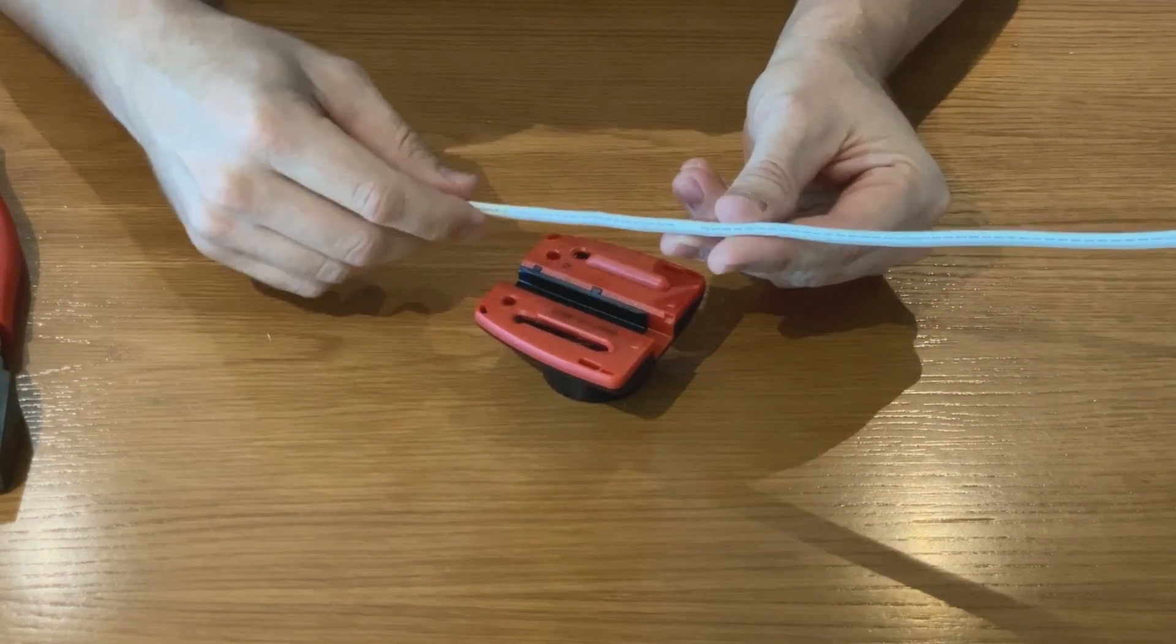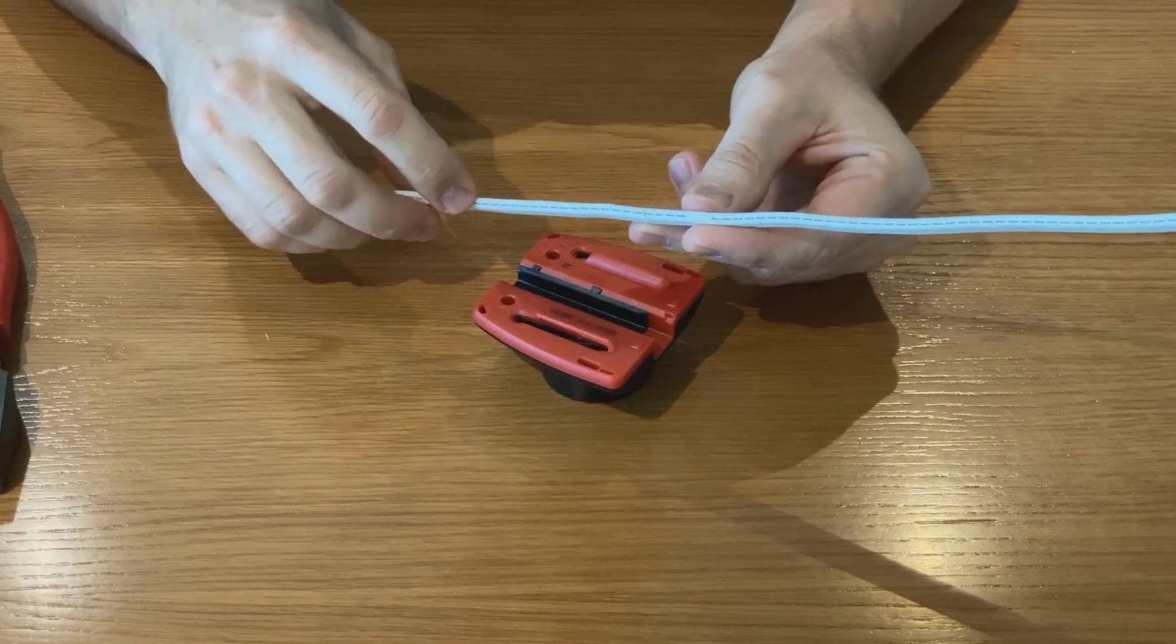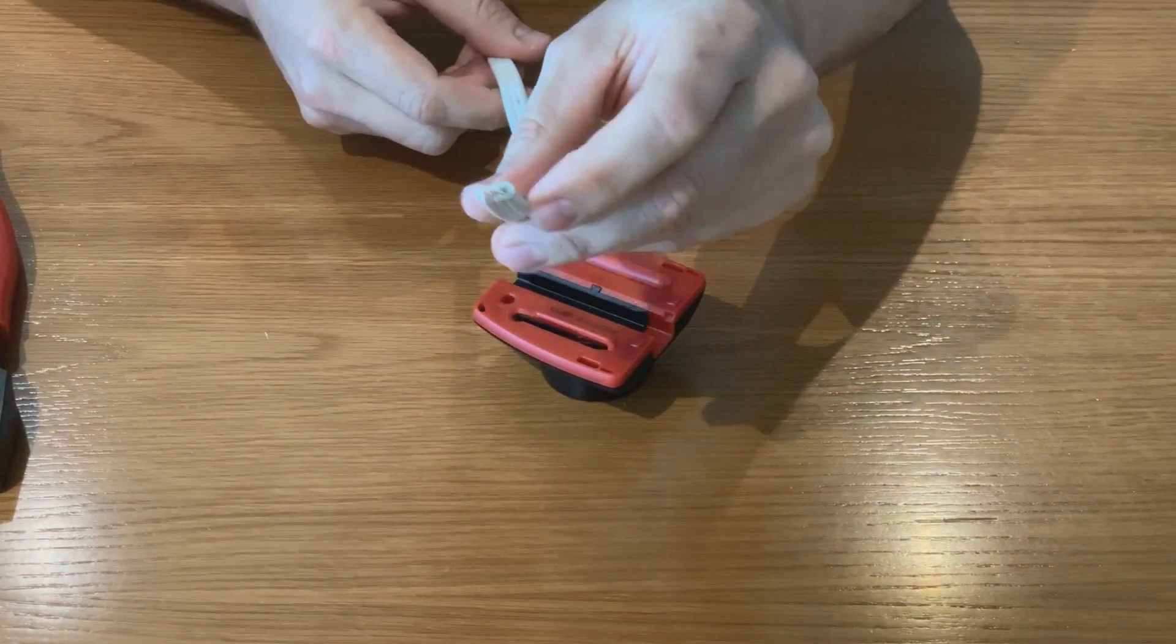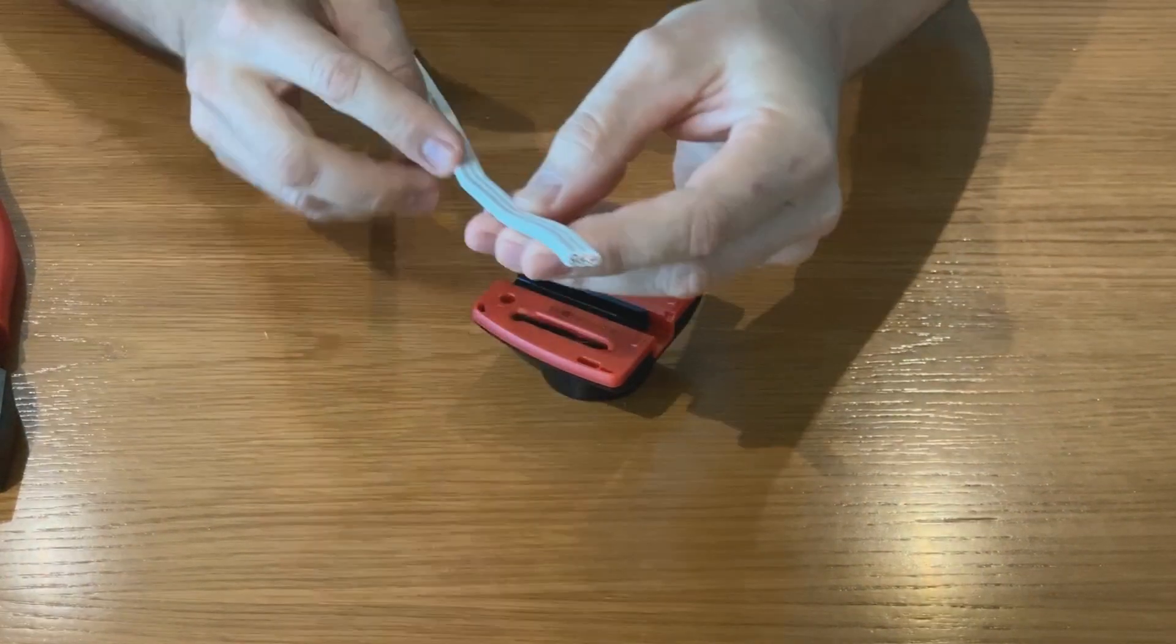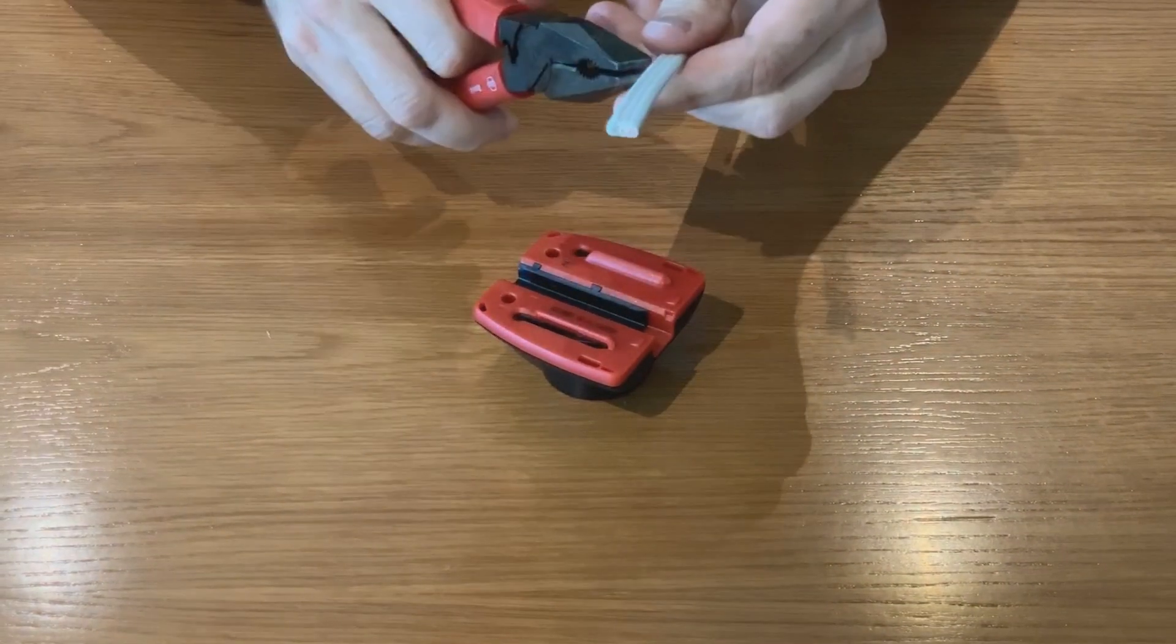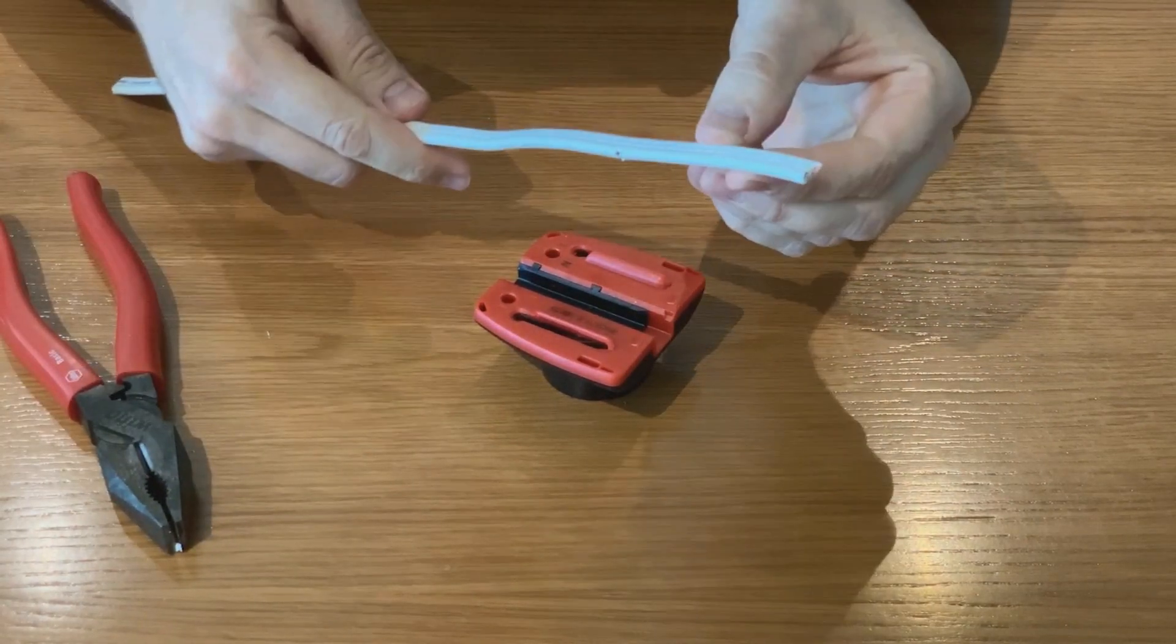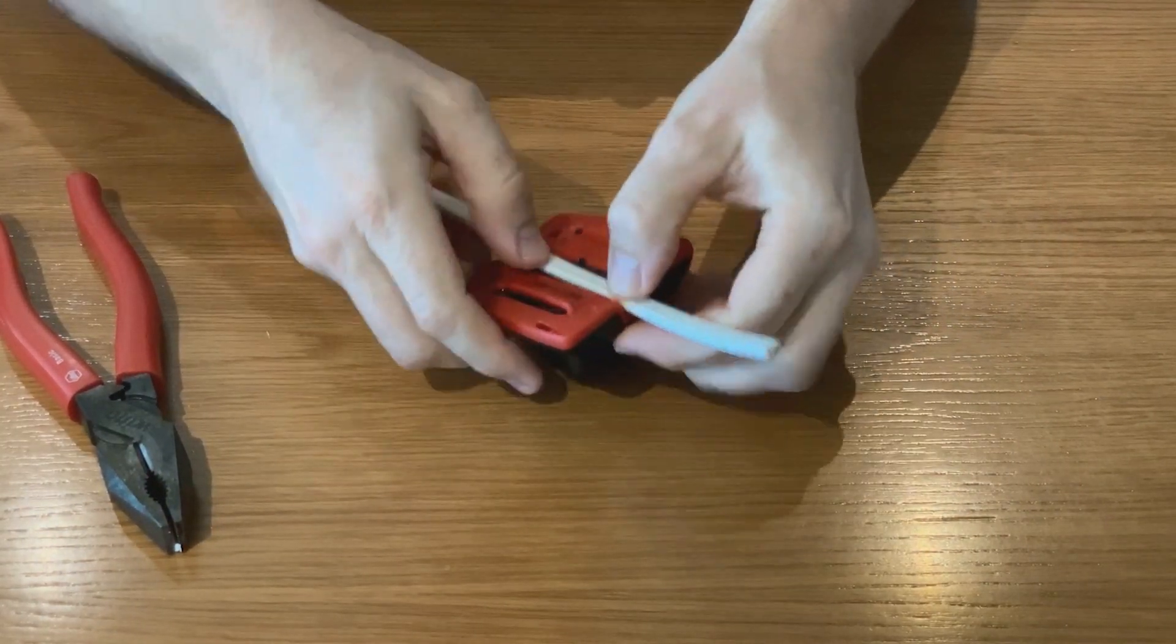Do check polarity before installation by using a marked active edge, by checking the end of the cable and which way the writing is on, or by nicking the outside sheath and then installing the cable into the tray.